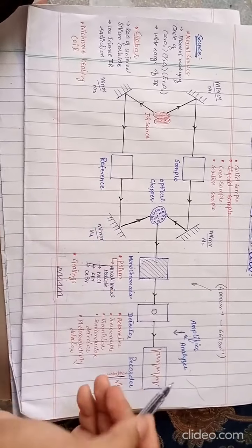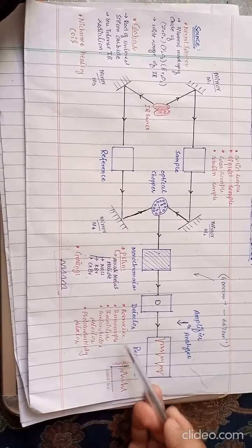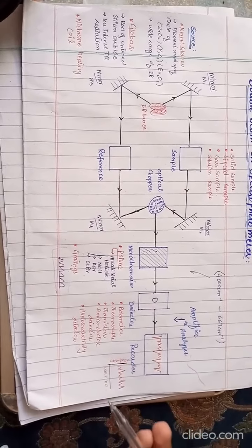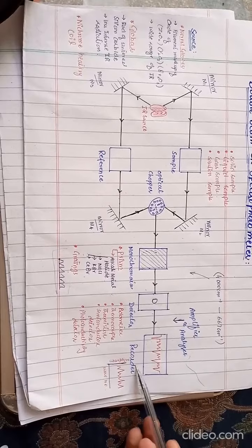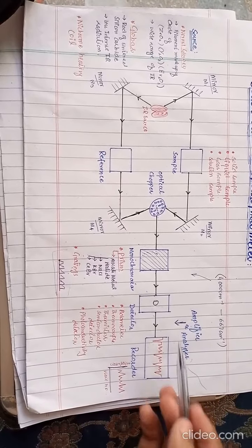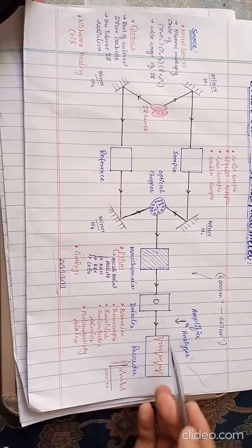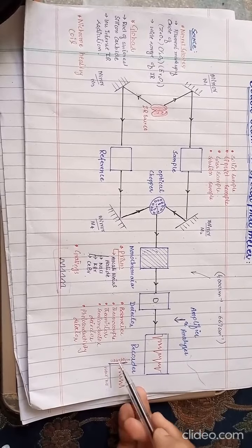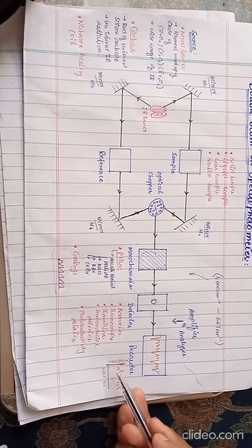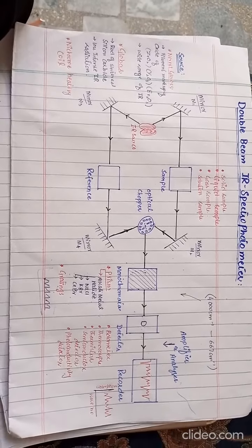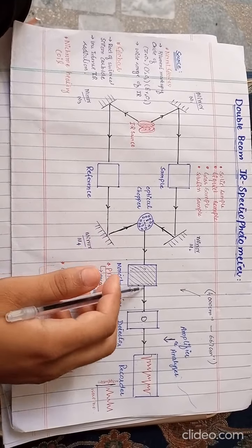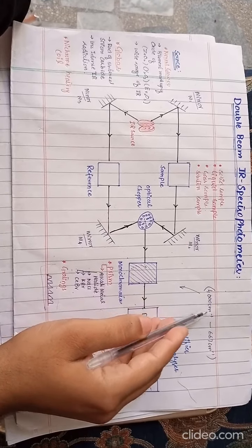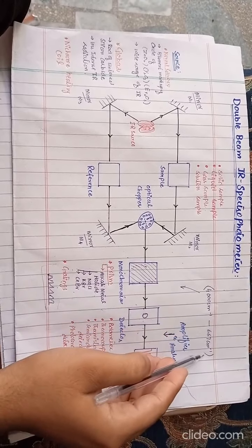Now the next component is the detector. The detector may be a bolometer, thermocouple, thermistor, semiconductor or photoconductivity detector. And the last one is the recorder. There the radiation coming from the detector can be recorded on the basis of the wave number and absorption value. The beam transferred from the monochromator to the detector has a range of 4000 cm inverse to 667 cm inverse.